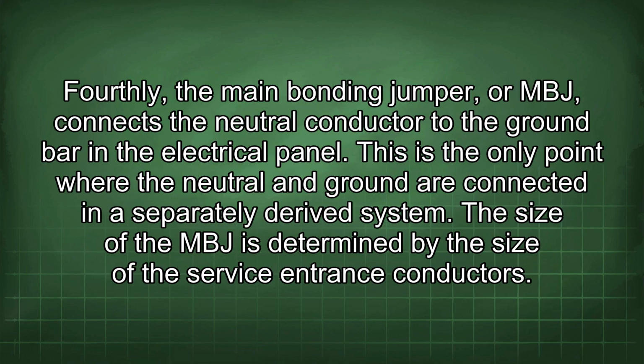Fourthly, the main bonding jumper, or MBJ, connects the neutral conductor to the ground bar in the electrical panel. This is the only point where the neutral and ground are connected in a separately derived system. The size of the MBJ is determined by the size of the service entrance conductors.